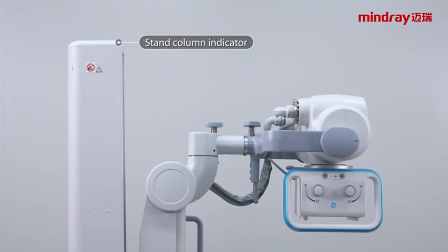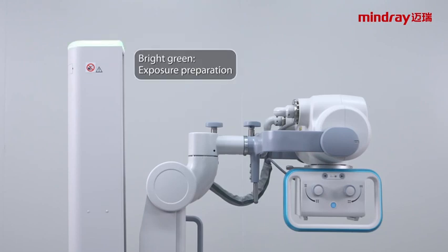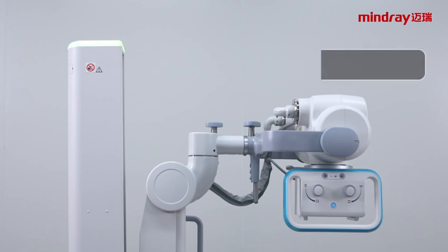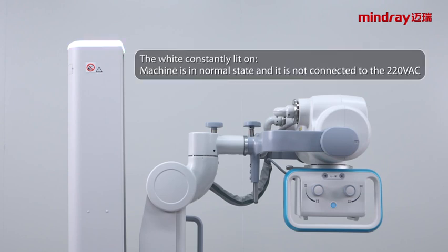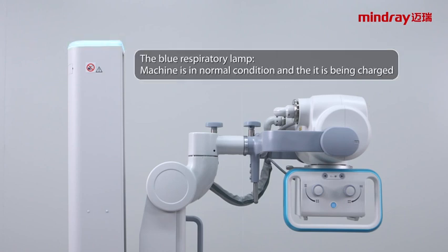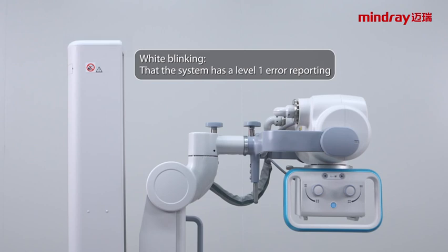Stand column indicator. Bright green, exposure preparation. Bright yellow, exposing. The white constantly lit on: the machine is in normal state and it is not connected to the 220 volt. The blue respiratory lamp: the machine is in normal condition and it is being charged. White blinking: the system has a level 1 error reporting. Red blinking: the system reports a level 2 or higher error.